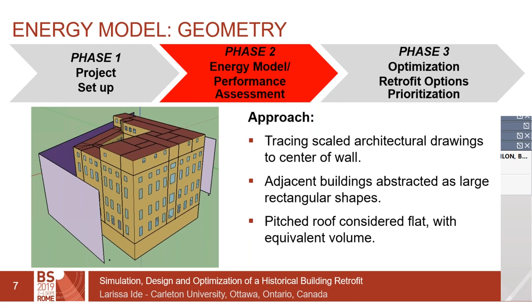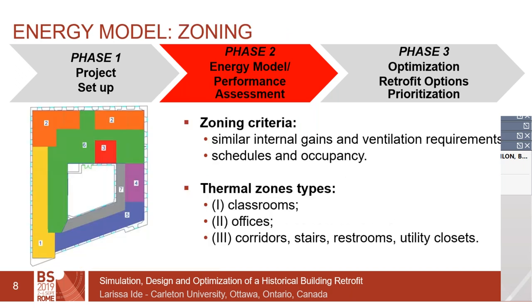We used an equivalent volume for the roof space. The zoning strategy grouped similar spaces with similar internal gains, ventilation requirements, schedules, and occupancy. This resulted in three main thermal zone types: classrooms, offices, and a third group combining corridors, stairs, restrooms, and utility closets. We initially had these last spaces separated, but that resulted in simulation runtimes of over 30 minutes — not feasible for the number of simulations planned for the sensitivity and optimization analysis. So we averaged and grouped them together.